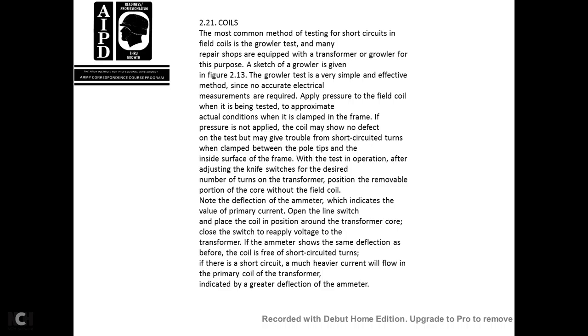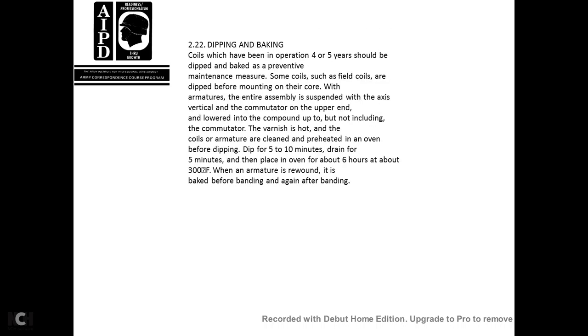Open the line switch and place the coil in this position around the transformer core. Close the switch. Reapply the voltage to the transformer. The ammeter shows the same deflection as before. The coil is free of the short circuit of the turns. If there is a short circuit, a much heavier current will flow into the primary coil of the transformer, indicated by a great deflection of the ammeter.